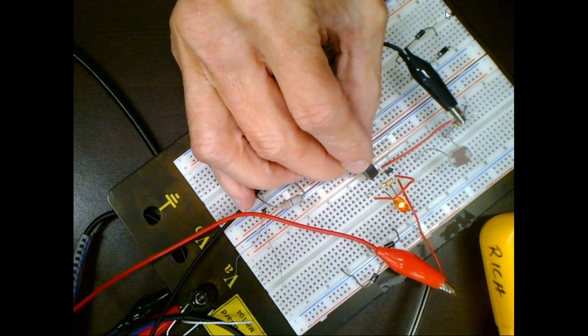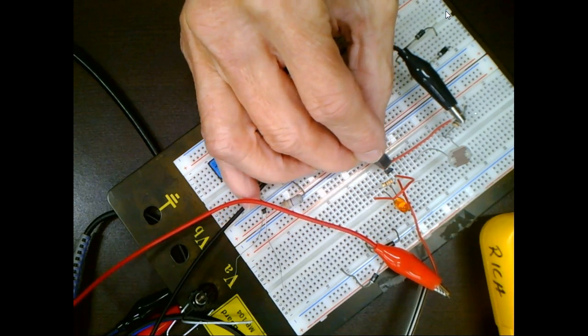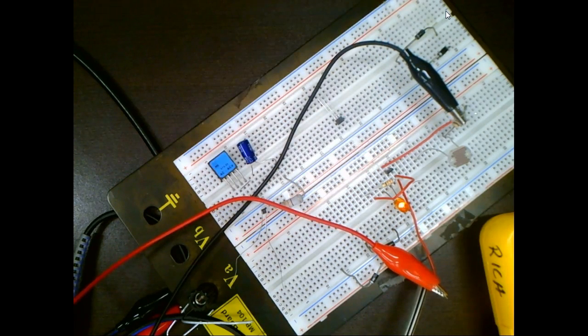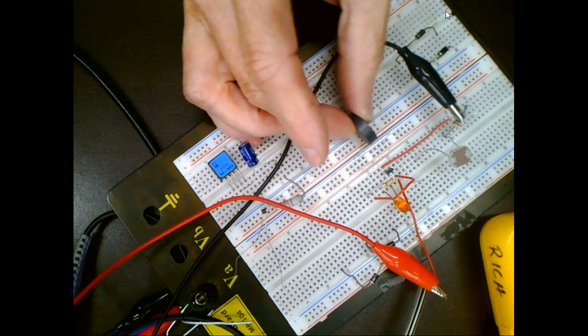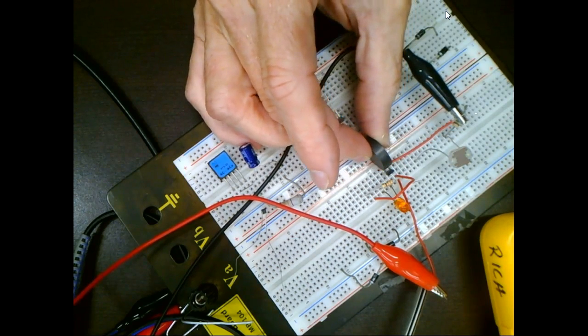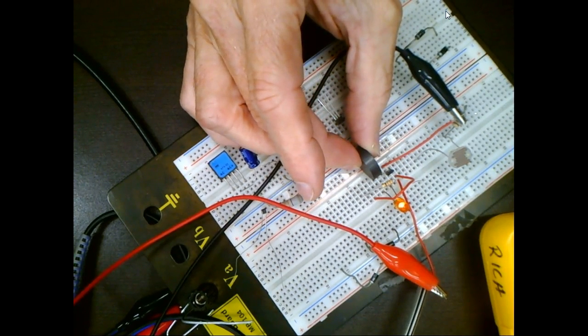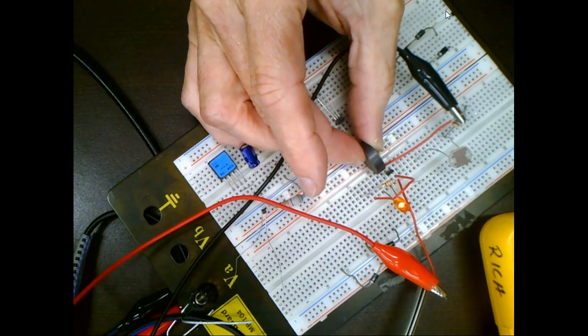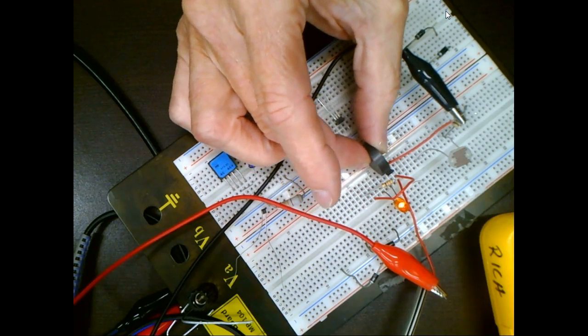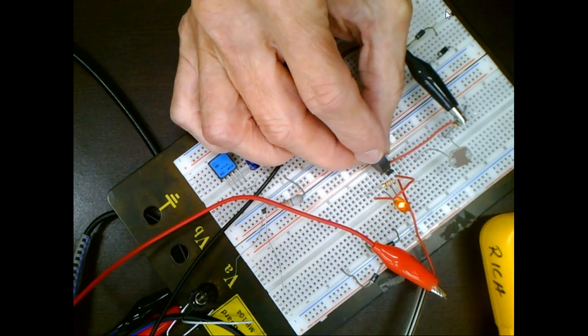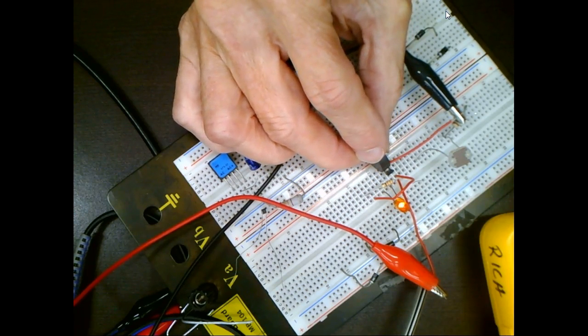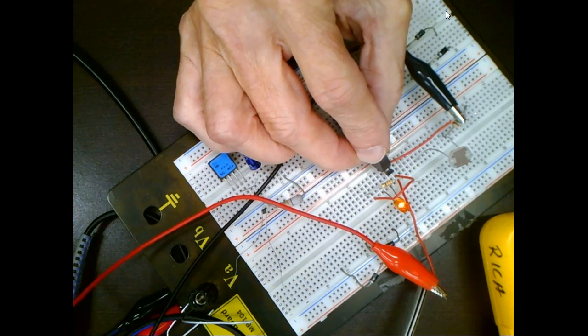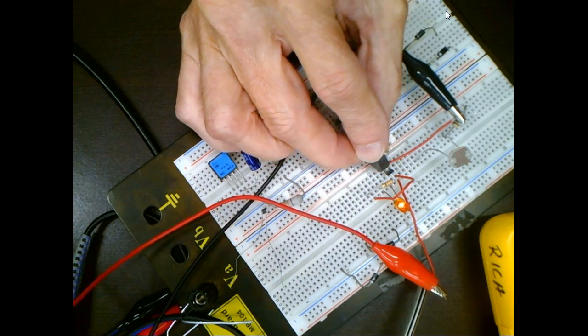See that? We use a lot of Hall effects over there on our cylinders to tell when they're extended and when they're retracted, and that's the way it works. So it's seeing this magnetic field when it hits a certain spot, right? You understand? And then when it goes away from it, it does what? Sorry, it should see the other field. So right now it's seeing one field, and then when it moves away from it, it turns off.